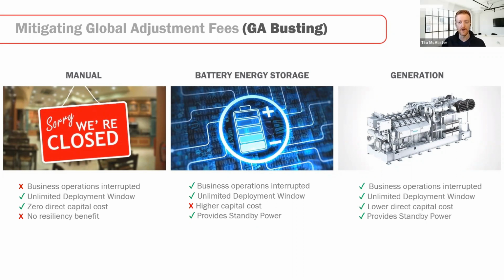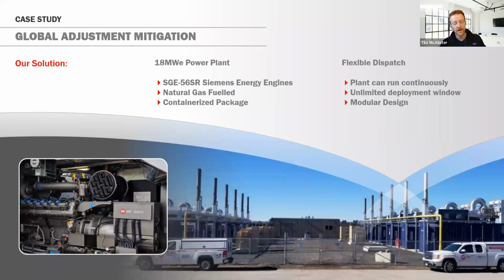Back to our little customer, they chose to go with generators. So we have an 18 megawatt power plant there now that turns on maybe 15 times a year, running for 6 or 7 hours each time, solely for the purpose of peak shaving this global adjustment charge. It also has some additional revenues available through the demand response program and a couple of other services it can provide to the ISO.